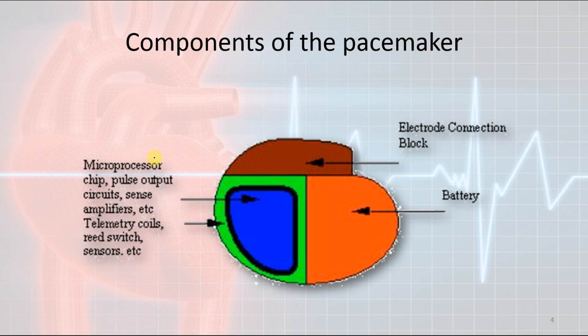Here's a couple pictures of the components of the pacemaker. This is an older one that I've had for a long time. You basically have an area right here, which is the battery. It's a very long-lasting battery. They usually last somewhere between 5 and 7 years. On another side over here, you have all your components. You have a microprocessor, pulse output circuits, amplifiers, all kinds of stuff over here to help run the pacemaker. And of course, usually somewhere else in the pacemaker, you have a place to plug your pacemaker wire into the pacemaker itself.